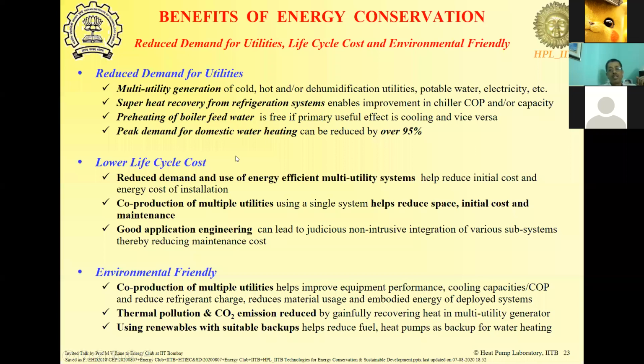As I said, for water heating, solar water heaters can give you hot water only when the sun is available, but waste heat recovery from refrigeration air conditioning systems can give you hot water anytime the refrigeration unit is on. Now, just imagine your cold stores in the kitchen in the hostels are also on all the time, throughout 12 months. So you can recover the heat from that for heating water, and that will be free. And in fact, that will also improve the performance of the cold stores in this case.